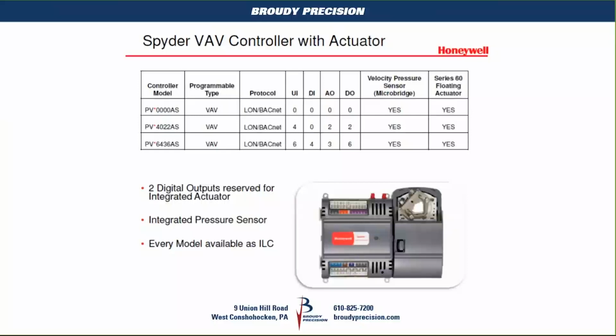And you'll notice that the 2 outputs that are required to operate the floating damper motor on the actuator are not included in the part number. Basically, when you buy an actuated Spyder, there are 2 that are dedicated for the floating damper motor, so they're not showing up in the part number. It's not a 4024, it's a 4022 because the 2 are dedicated.